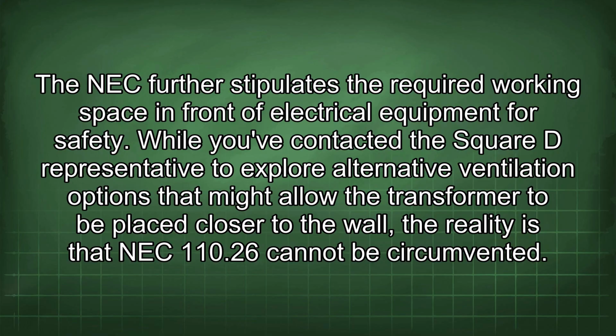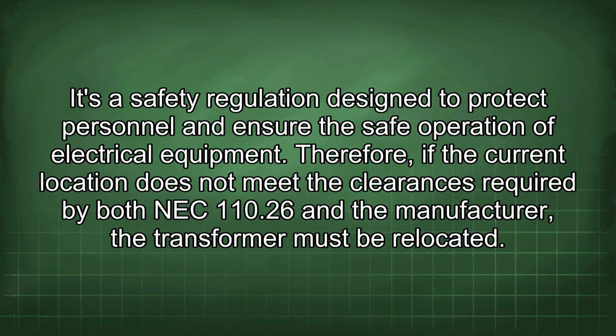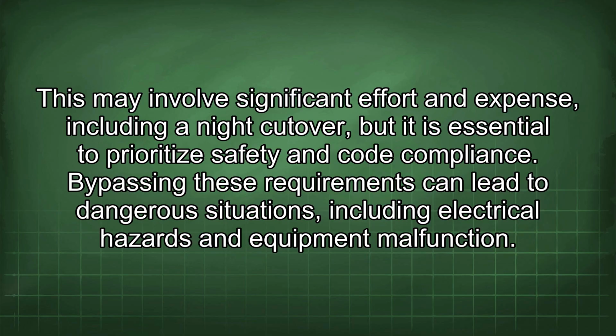While you've contacted the Square D representative to explore alternative ventilation options that might allow the transformer to be placed closer to the wall, the reality is that NEC 110.26 cannot be circumvented. It's a safety regulation designed to protect personnel and ensure the safe operation of electrical equipment. Therefore, if the current location does not meet the clearances required by both NEC 110.26 and the manufacturer, the transformer must be relocated. This may involve significant effort and expense, including a night cutover, but it is essential to prioritize safety and code compliance. Bypassing these requirements can lead to dangerous situations, including electrical hazards and equipment malfunction.